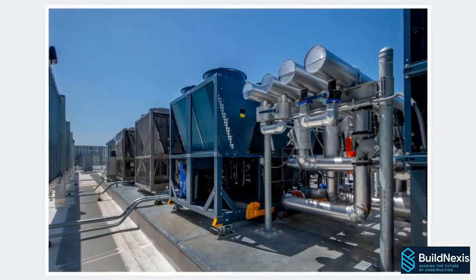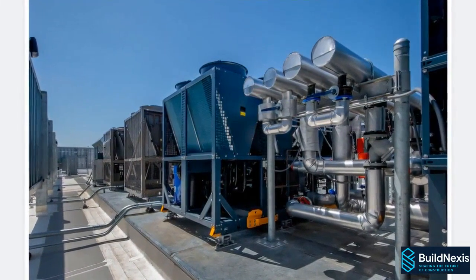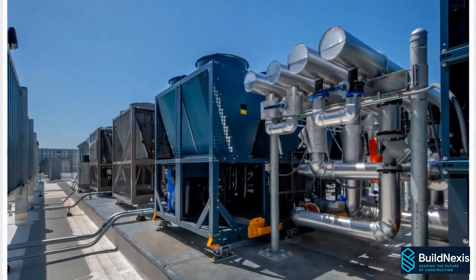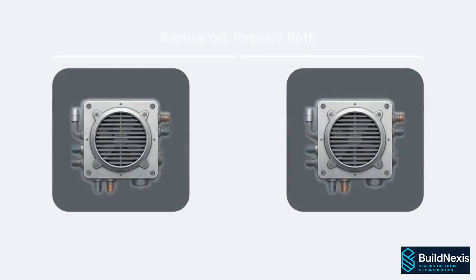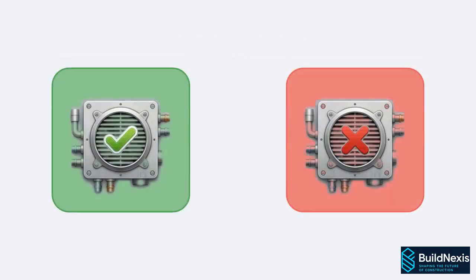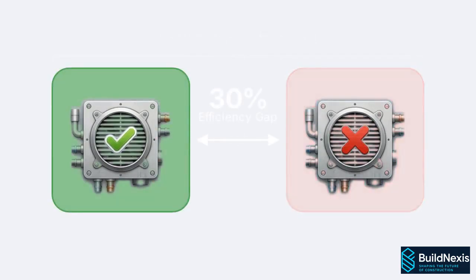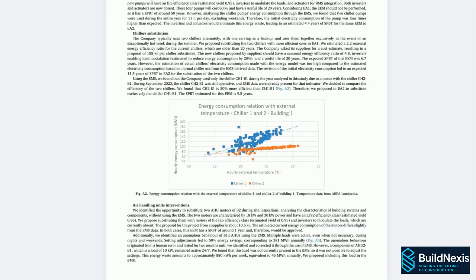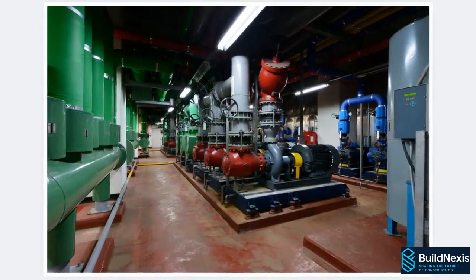The monitoring data immediately contradicted the model's findings regarding the main cooling units. While the software demanded replacing both chillers, the sensors showed only one was underperforming. A scatter plot of energy consumption relative to external temperatures revealed a clear 30% efficiency gap between chiller 1 and chiller 2, meaning only the least efficient unit actually required replacement. The audit then turned to the chiller pumps.